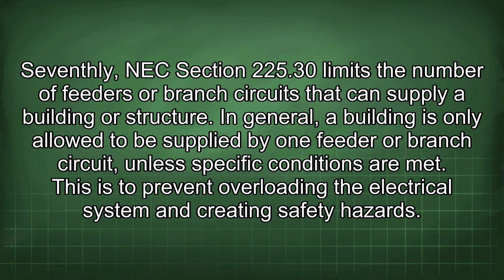Seventhly, NEC Section 225.30 limits the number of feeders or branch circuits that can supply a building or structure. In general, a building is only allowed to be supplied by one feeder or branch circuit unless specific conditions are met. This is to prevent overloading the electrical system and creating safety hazards.